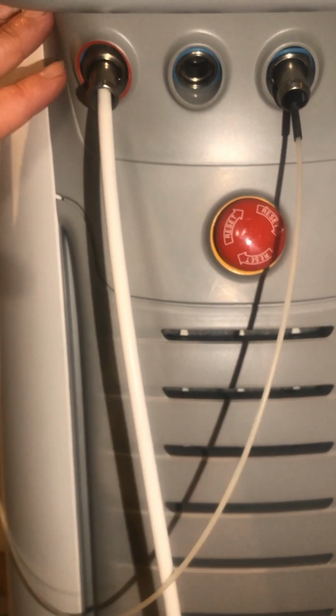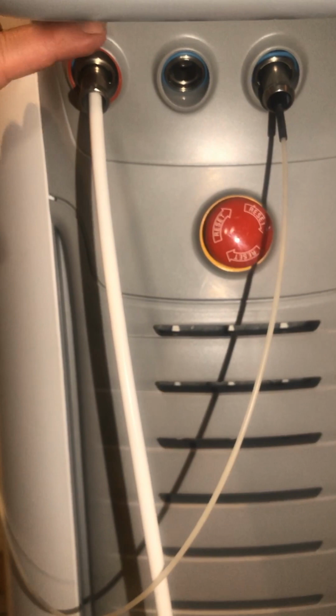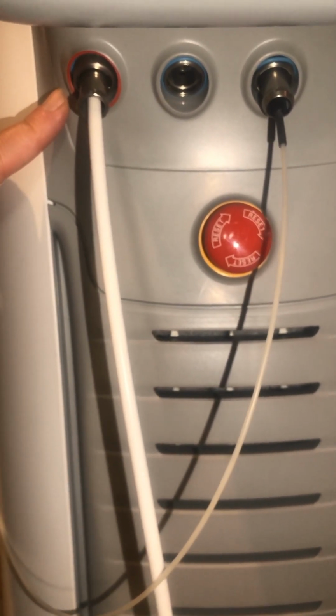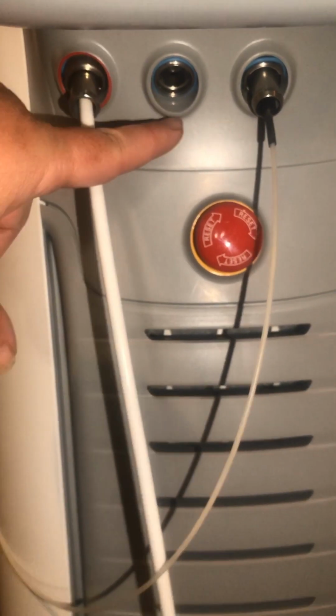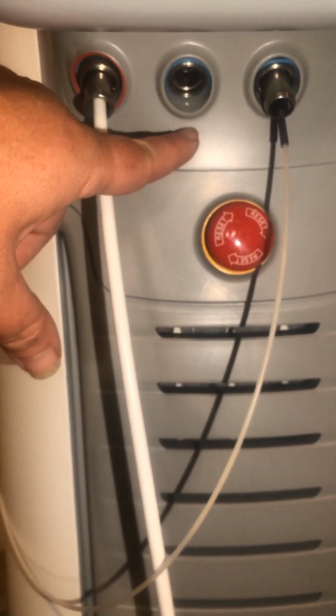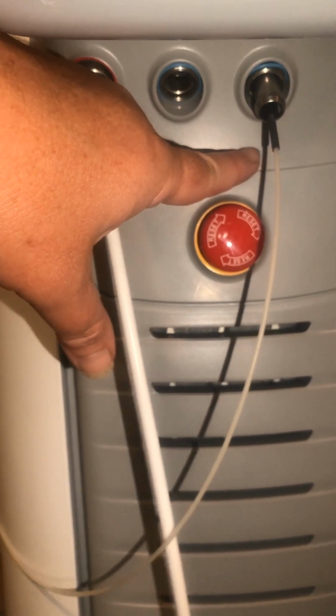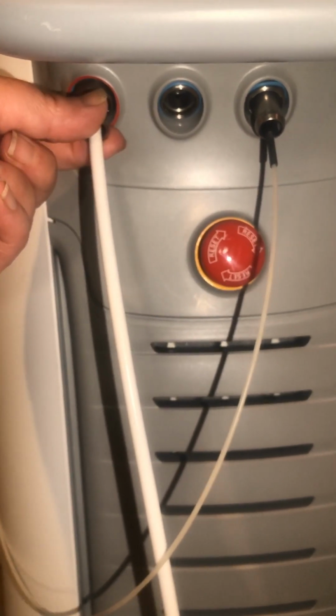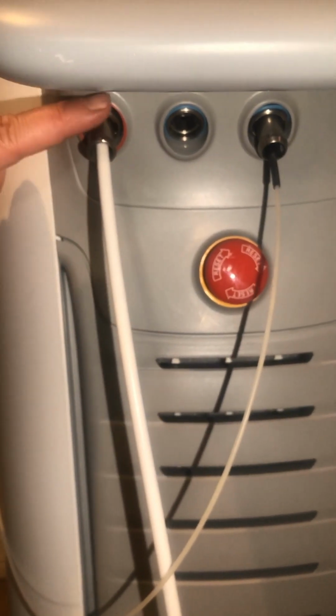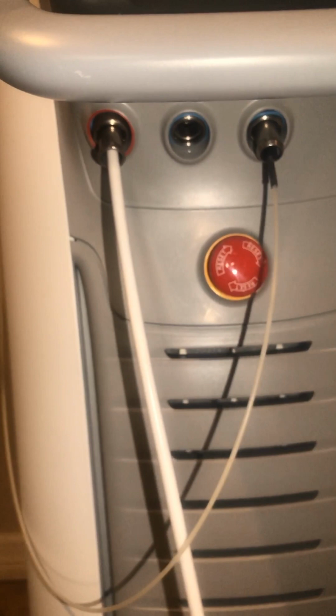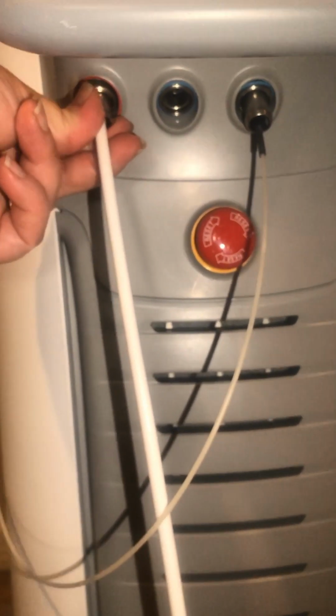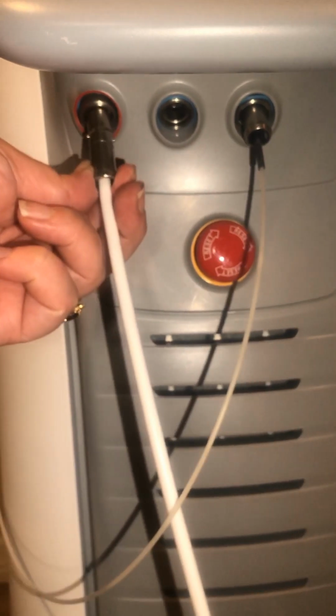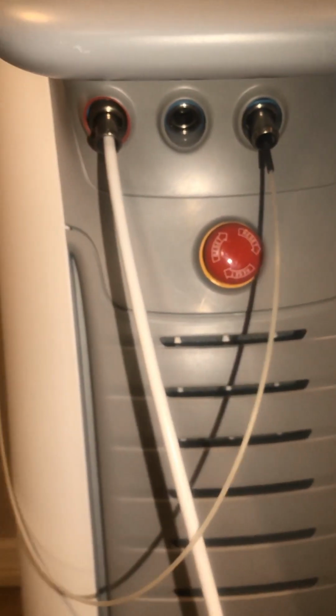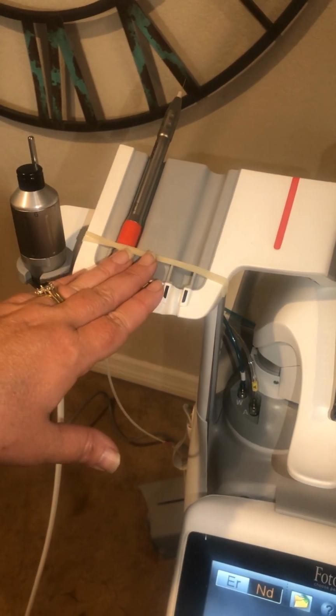Now this also is connected to a fiber, and so that fiber goes down and it connects into the ND-YAG ports. These are all of the ports where the laser energy comes out of for the ND-YAG. The one with a red circle around it is your active port for your R30A and the 300 fiber. This middle part is for the 200 micron fiber and the Genova handpiece. And then this is your parking spot. So whichever handpiece that you're using, either the R30A or the 300, whichever one you're using needs to be in this active port, and the one that you're not, you would place in the parking position, okay? Now to change these, you want to push up and to the left to release it, and then to seat it, you push up and turn to the right to lock it in place. It's that simple.